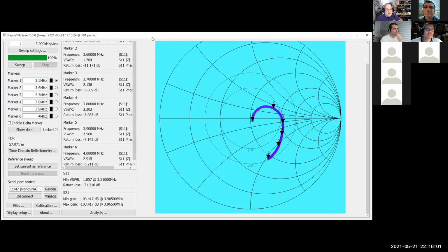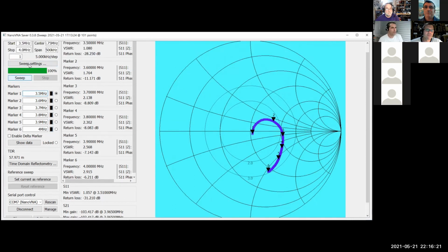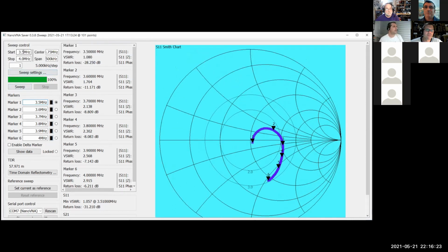So I can just say, all right, I'm going to make a calibration with 100 feet of coax, another calibration with 200 feet of coax, within reason. But I think it's fair to assume that every time we switch the frequency range from start to stop, say I wanted to go from 430 to 440, every time we have a different frequency envelope, we need to calibrate. Oh yes, but I would do that ahead of time and save all those frequencies on my computer. So I did that, like 3 months ago. Yeah, so I think that is the way to go, Ricardo.